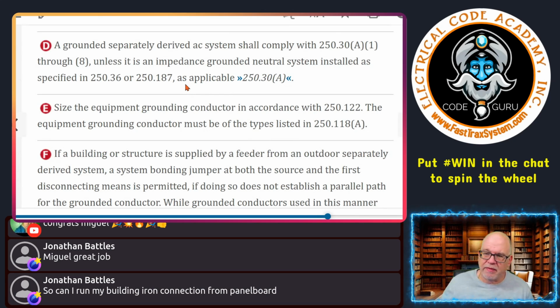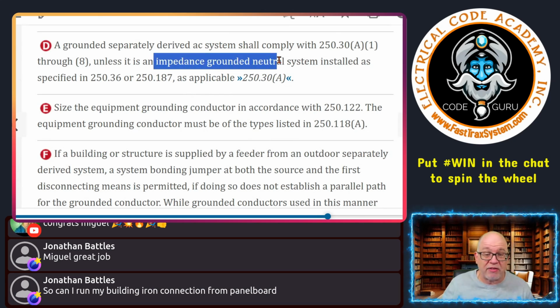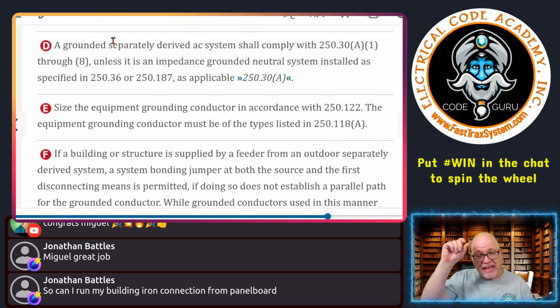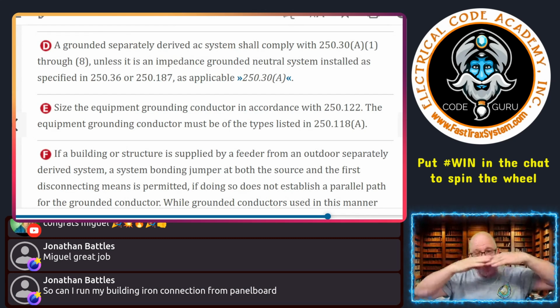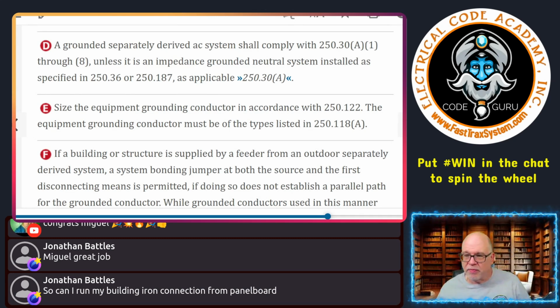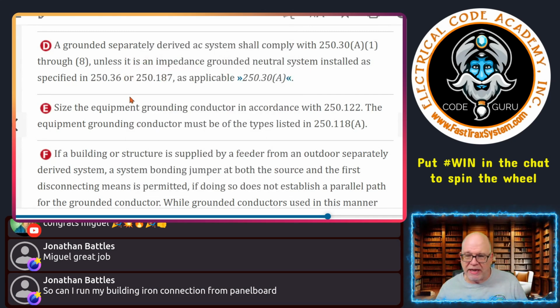Actually, let me take that back. This impedance grounded neutral is actually installed between the XO. It makes a connection in there and adds this impedance so that things don't trip off prematurely when dealing with those types of systems. Either way, you do have to follow their specific rules in 250.36 or 250.187.